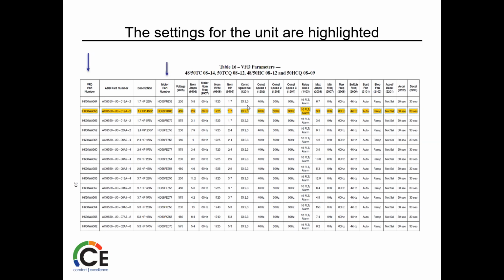If I'm helping you, I try to do it in order, though you can see that the list isn't terribly in order. You don't have to do it in order. I don't know, I'm weird, and that's how I give it to you. So we're going to go through and check voltage. If we've got a 460 unit, make sure we're set up for 460. We're doing amps, right? Motor frequencies. Here's that constant speed. So here's your D1, D2, and D3. D1 is going to be 40 Hertz, D2 is 60, D3 is 60.